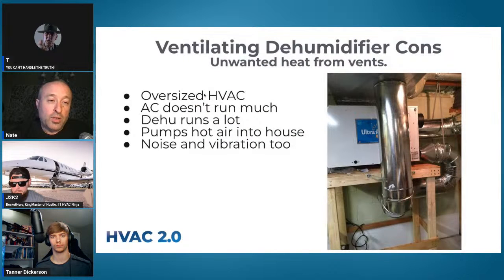What happened was his air conditioner is too big, so it didn't run much. The dehu runs a lot, and he complained a fair amount about hot air coming out of the ducts on that side of the house, because we hadn't put it close to the equipment, so it didn't have a chance to go through. Whenever we've put these on 1 or 2 stage equipment, we've had challenges with hot air coming out of the vents. So like I say, friends don't let friends buy single stage.